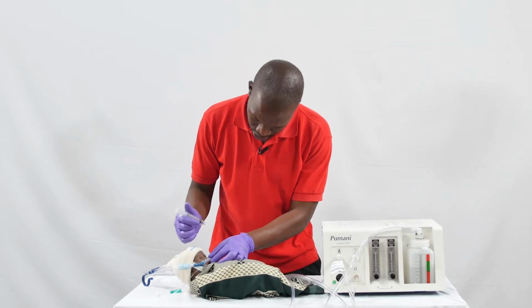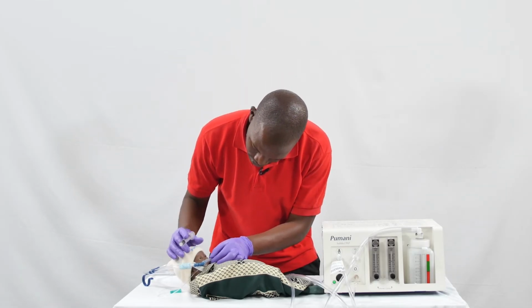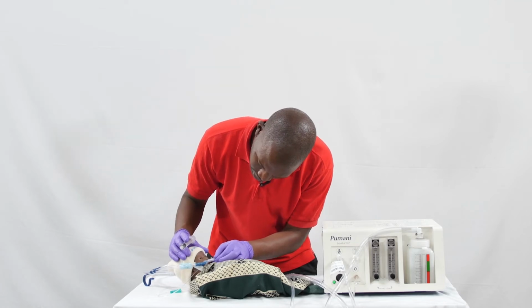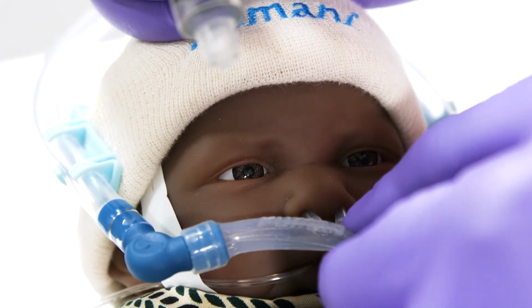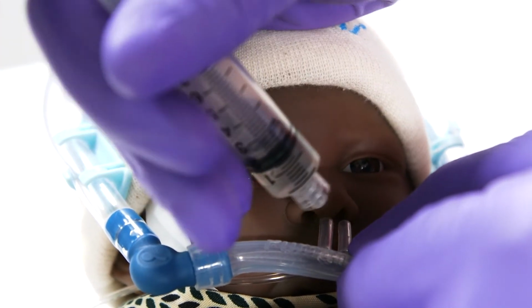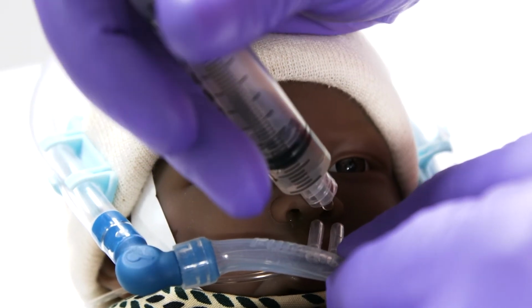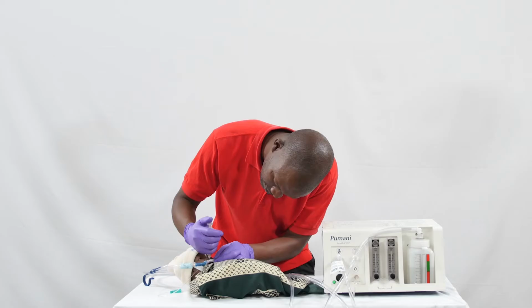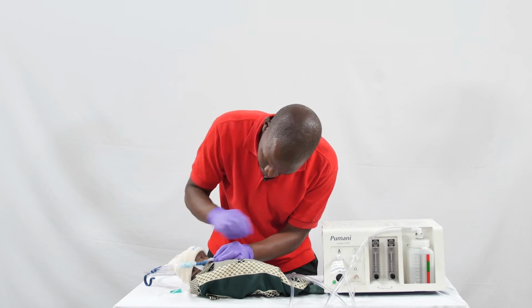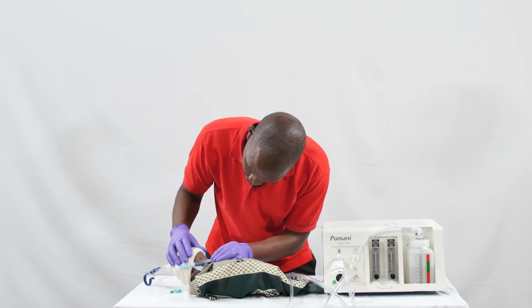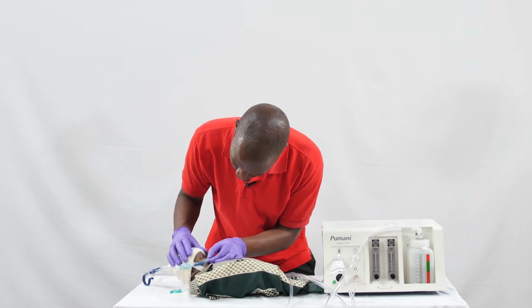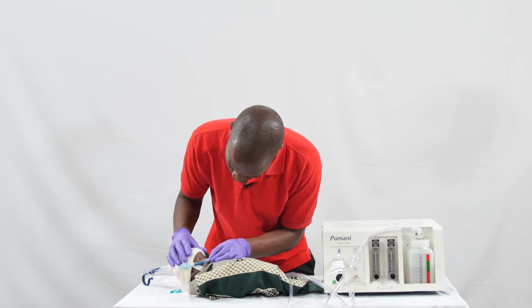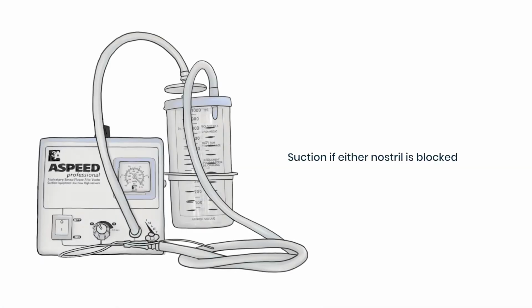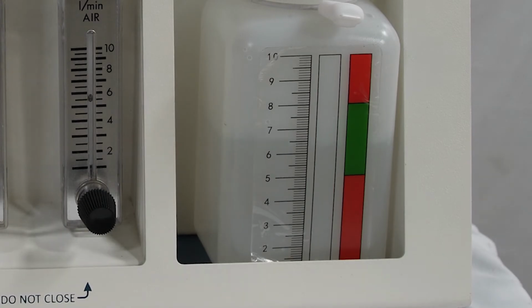You need to add saline drops. You need to put a saline drop in each of the nostrils. Briefly take out the prongs to do this. The drops are very important to stop the baby's nose from drying out, which can lead to complications. Make sure that the septum is not damaged. If either nostril appears blocked, then you need to suction the baby. When you put back the prongs, make sure the water starts to bubble.